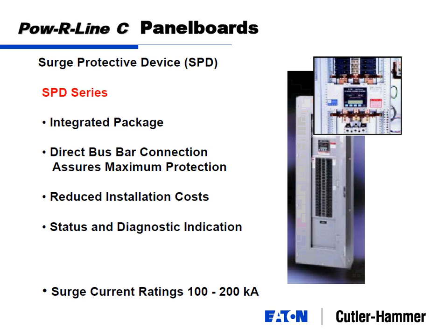So the two kinds, then: you've got the lightning, one hit, you could take it out, and then you've got the internal building generation, which is jabs. And I mentioned 200,000 amps coming. Maybe it's only 50,000 amps coming. It's one big shot though. On the inside of the building, maybe you're talking 1,000 to 1,500 amps or volts coming in, and it's just pounding. Just jab, jab, jab, and after 1,000 jabs, you're probably going to hit the canvas. And those are the two ways that transient overvoltages can affect your equipment.